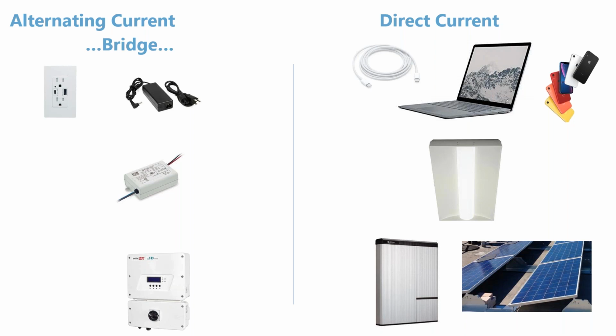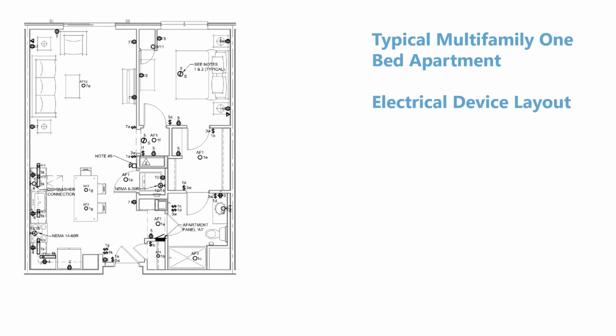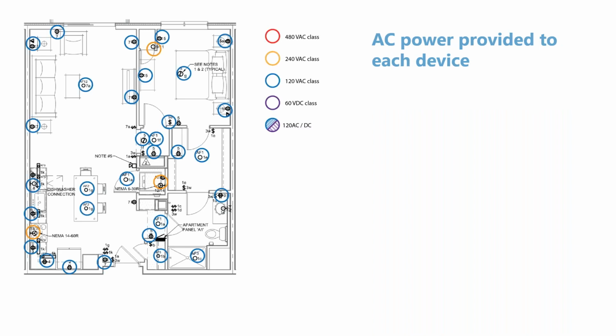So by adopting or looking towards an all-DC power topology, we can look to remove all of these accessory devices that are only there because of the legacy of AC being the prevalent power distribution topology. So let's take a look at a typical one-bedroom apartment and look at the devices that require power. So here's an electrical layout, and I've added some annotation here to suggest what the power demands are of all of those devices: receptacles, lights, appliances, HVAC equipment, and ultimately the voltage ratings that each of those devices requires to operate.